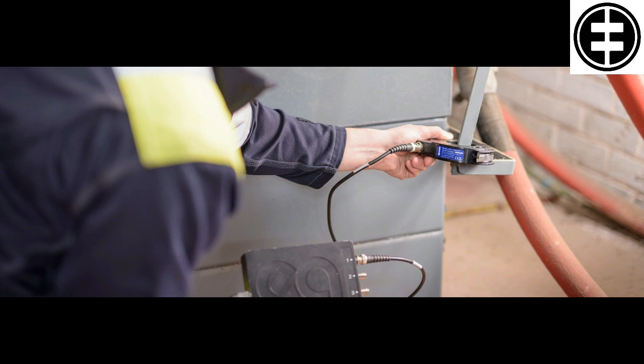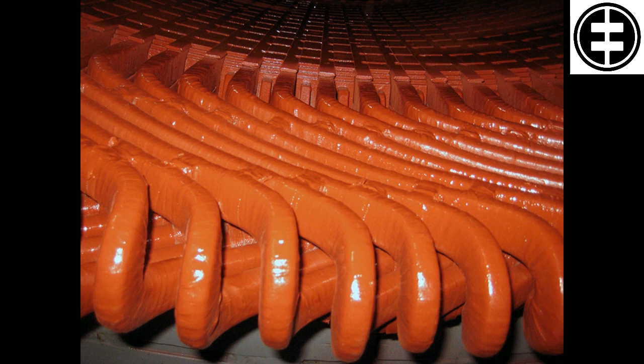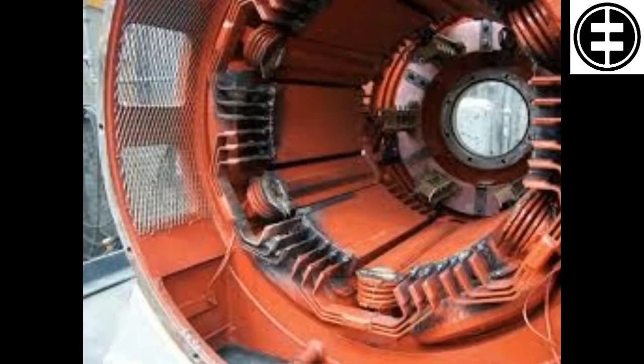If monitoring reveals a rising trend in PD levels, this may indicate that a problem exists and action should be taken to identify the source of the PD. If the increase in PD is due to ambient factors, such as a dirty or wet winding, the solution is simply to clean and/or dry the winding. The aging process is highly dependent on temperature, and if high temperatures are causing accelerated aging, the cooler can be serviced to bring them back down to normal levels.